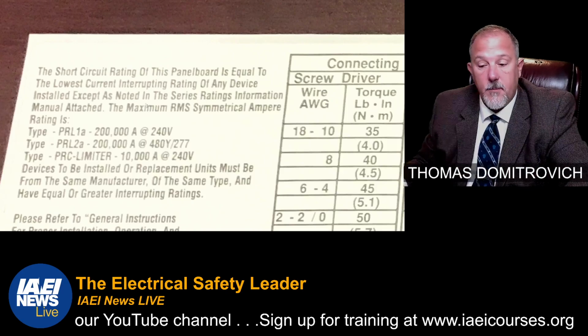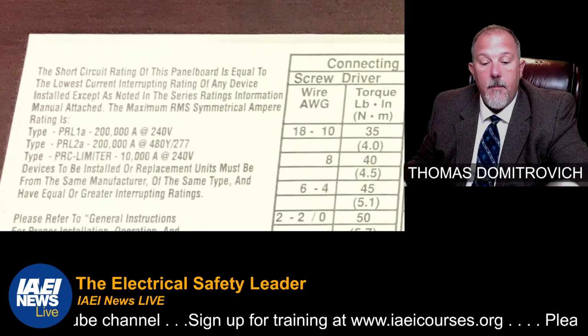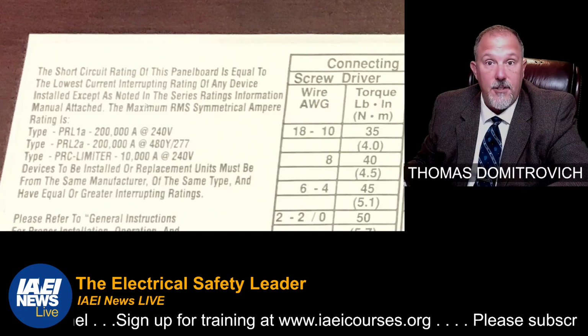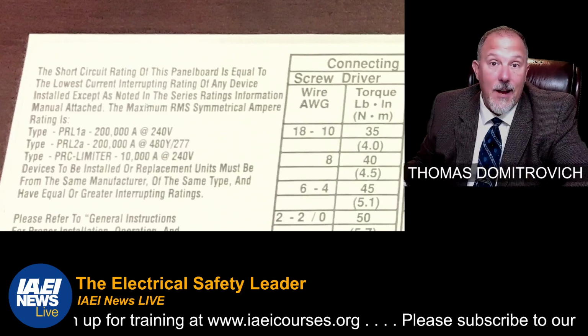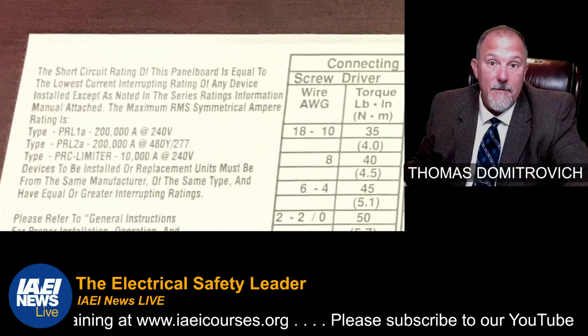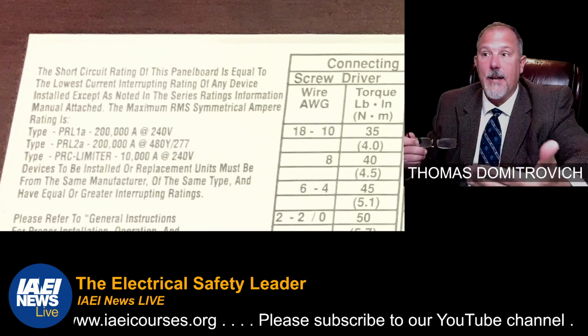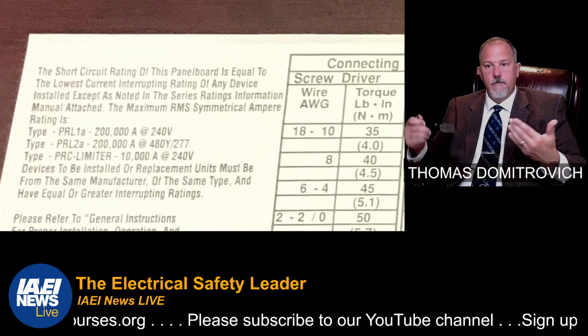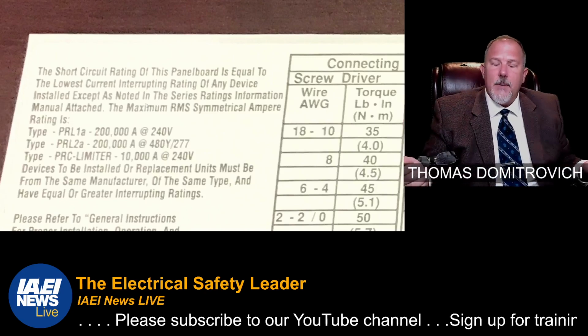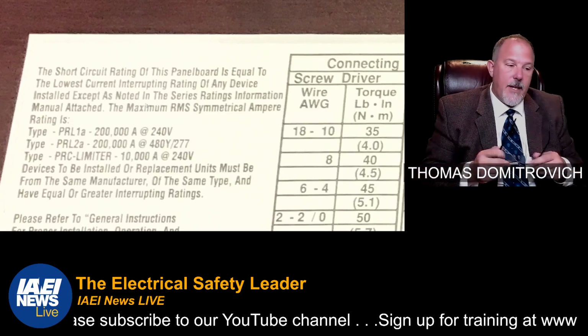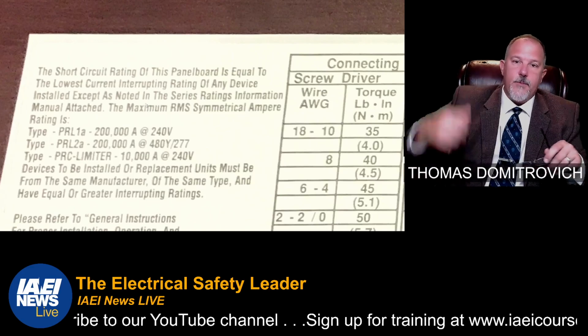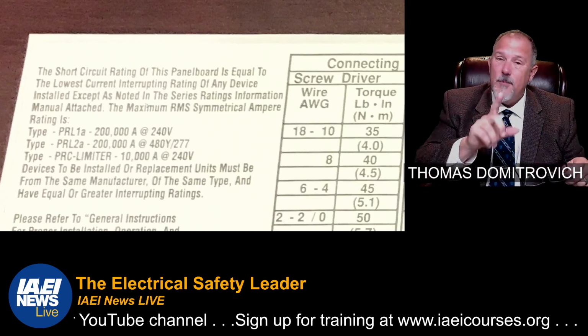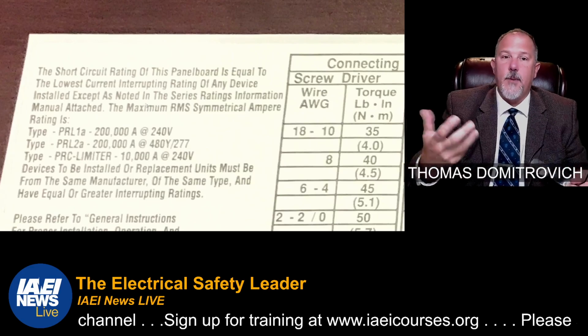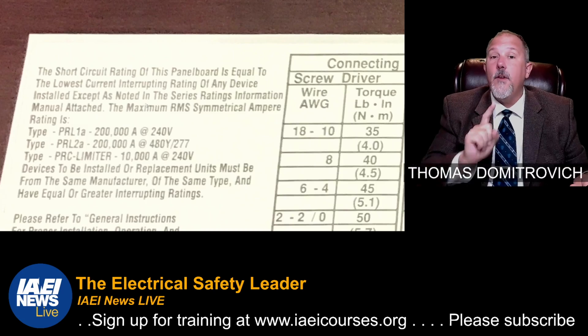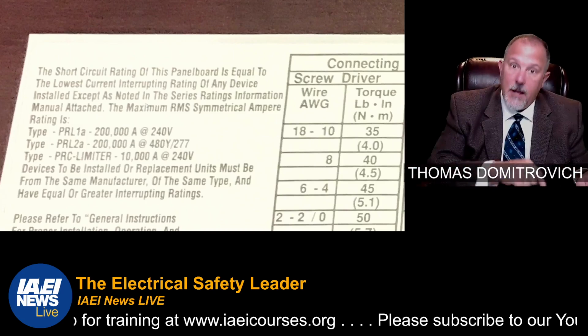But when it comes to circuit breakers, my interrupting ratings change, and they'll fit in the same slot, right? So you take out a 22K circuit breaker, you go down to the supply house, and you say, I need a 20 amp circuit breaker. It's 22K, but do you think that they're going to look at the side of the breaker and go, oh, this is a 22K? Now, hopefully what they do is they look at the catalog number.